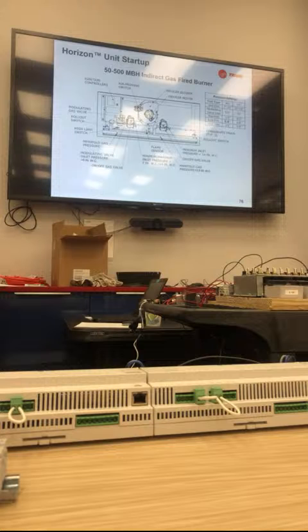I think we should with the unit. Yeah, we ship with the unit now, also. Once you're done, you hold both buttons, it's set. Hold the right, light comes on, stays lit. Press the right, it increases, left decreases. Once you get to 3.5, you hold it, and then it sets itself. So that's how you can set this valve. It's very, very easy. Again, we'll look at that tomorrow. Yeah, so we go to UC units.